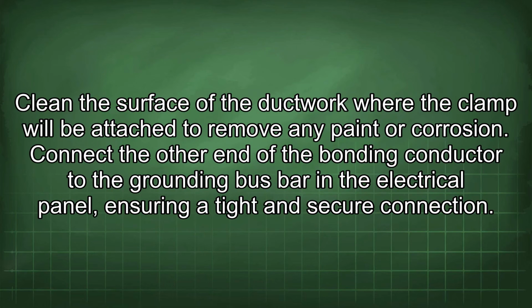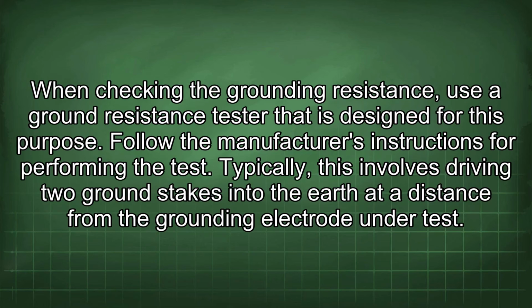Clean the surface of the ductwork where the clamp will be attached to remove any paint or corrosion. Connect the other end of the bonding conductor to the grounding bus bar in the electrical panel, ensuring a tight and secure connection. When checking the grounding resistance, use a ground resistance tester that is designed for this purpose. Follow the manufacturer's instructions for performing the test.